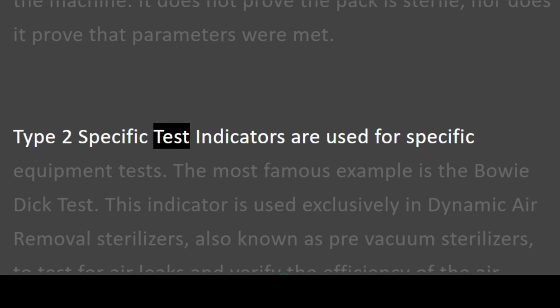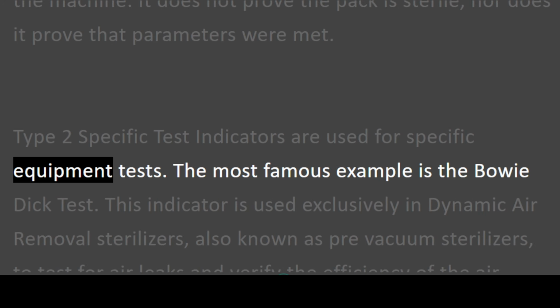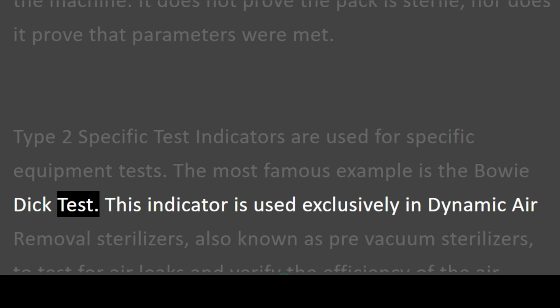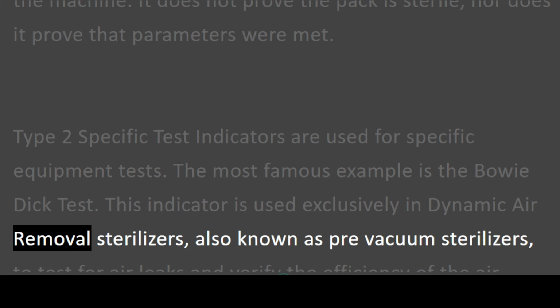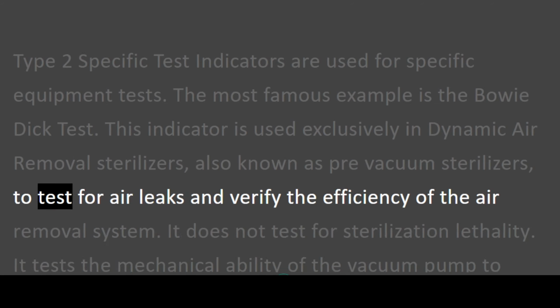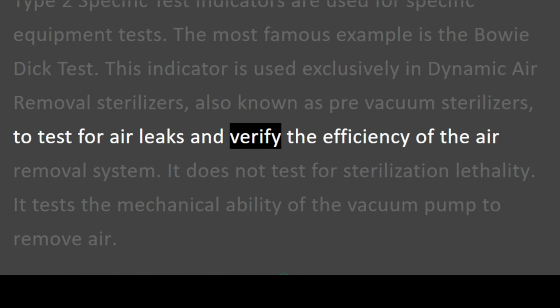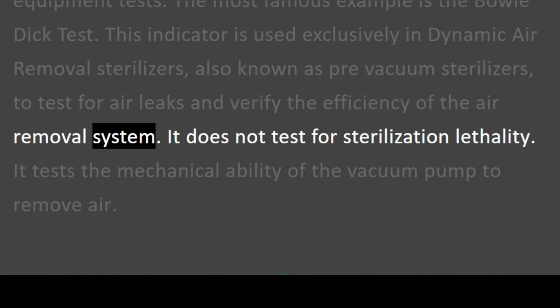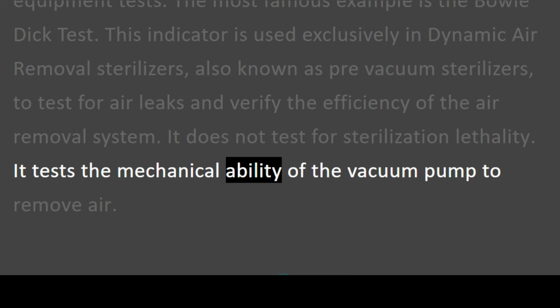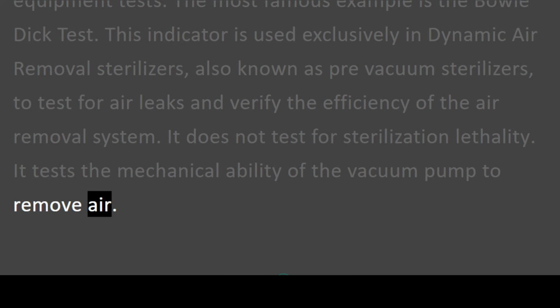Type 2 specific test indicators are used for specific equipment tests. The most famous example is the Bowie-Dick test. This indicator is used exclusively in dynamic air removal sterilizers, also known as pre-vacuum sterilizers, to test for air leaks and verify the efficiency of the air removal system. It does not test for sterilization lethality. It tests the mechanical ability of the vacuum pump to remove air.